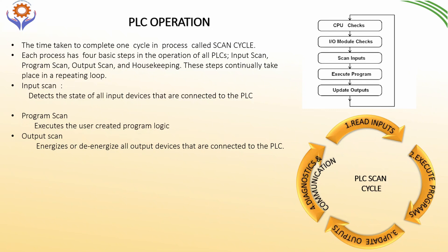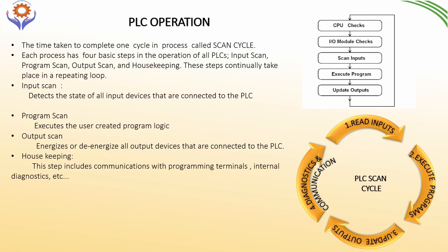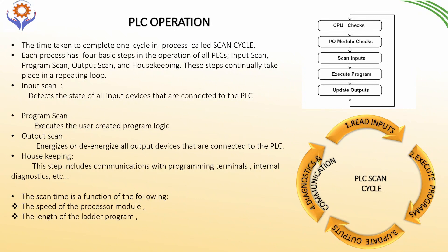And housekeeping — otherwise we can call it diagnostics and communication systems. These steps include communication with programming terminals, internal diagnostics, etc. The scan time is based on the following factors: speed of the processor, length of the ladder logic program, the type of instruction executed, and the actual ladder true or fault conditions. Based on these factors, the scan cycle will vary.